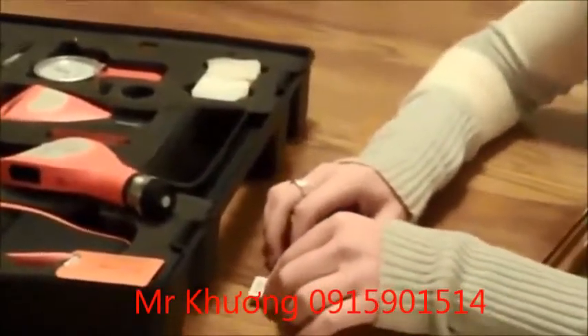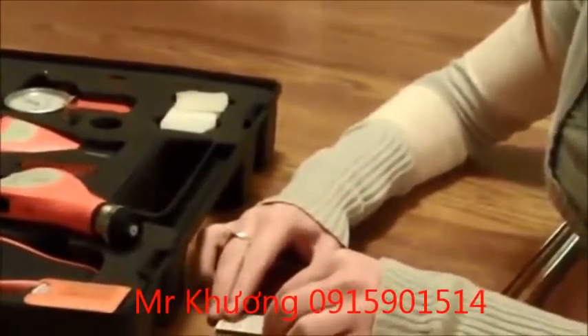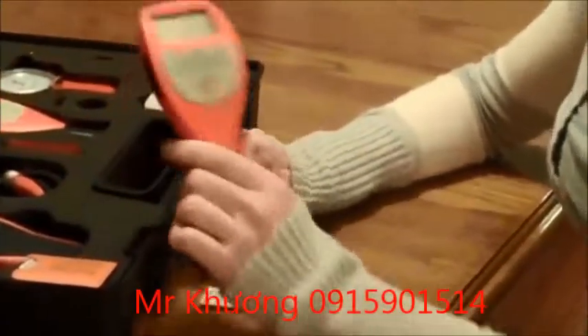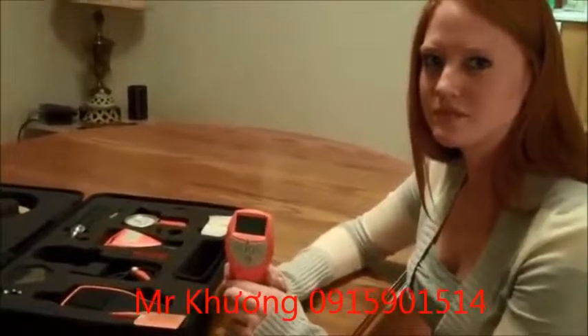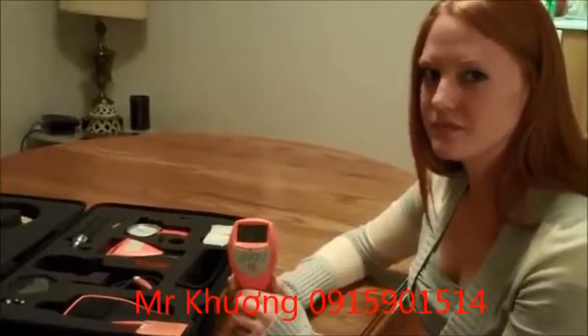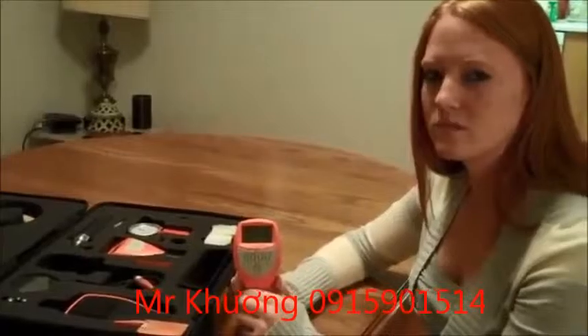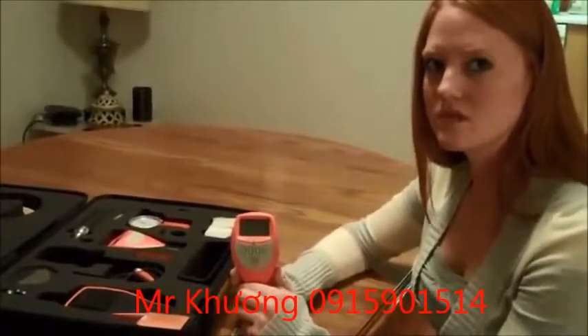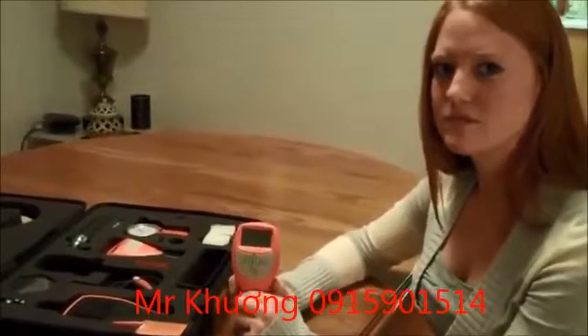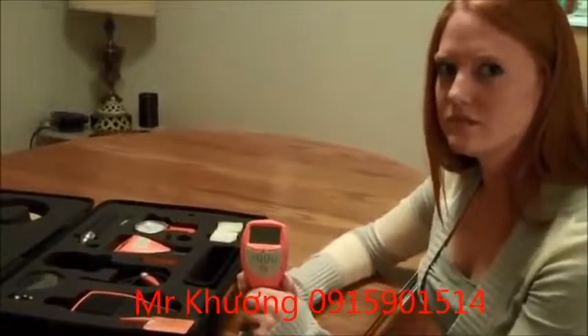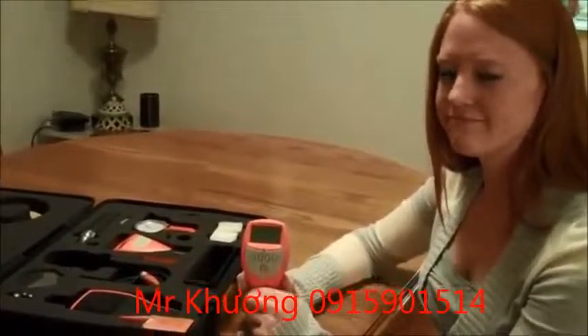9.9 mils. Yeah, now when you're choosing your calibration shim or foil, you want to make sure that you always choose a shim that is thicker than the coating that you're going to be measuring. For instance, if you know that you're trying to target 5 mils on your steel parts, you would want to choose a shim, say, at 10 mils. A good rule of thumb is just go twice your expected thickness, and that way you can measure anything from 0 to 10 mils, so if you ever spray a bit, you can get an accurate reading.